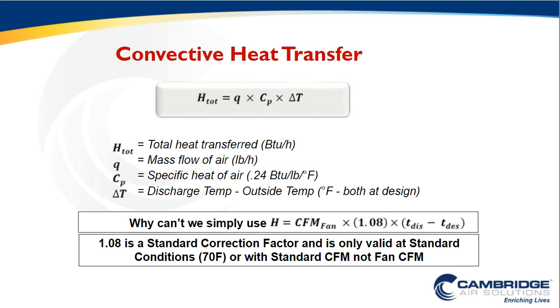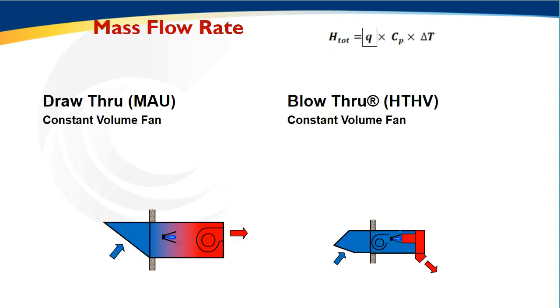However, let's talk about our systems here. We're talking about the difference between 0 degrees and 120 degrees. Do we think there's going to be some element of different densities? Do we think that 1.08 standard correction factor will work? Well, let's look at it. And let's look at this convective heat transfer and see what the difference is in the ability to transfer heat by processing different densities of air.